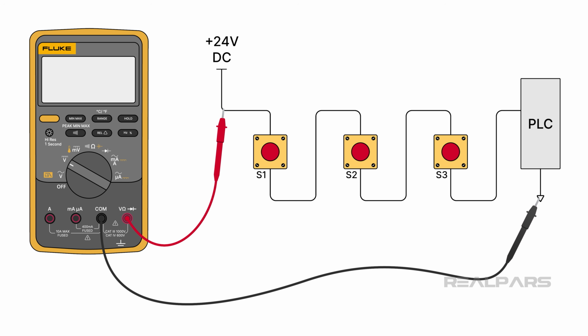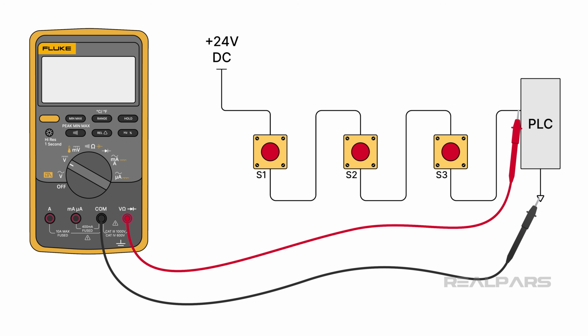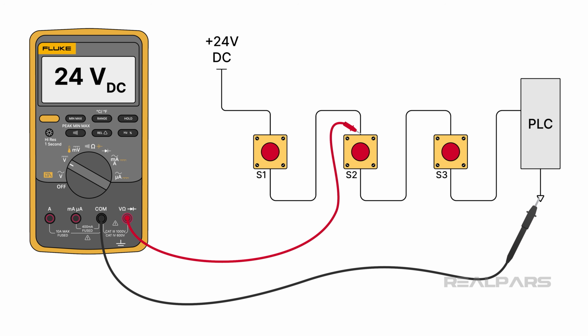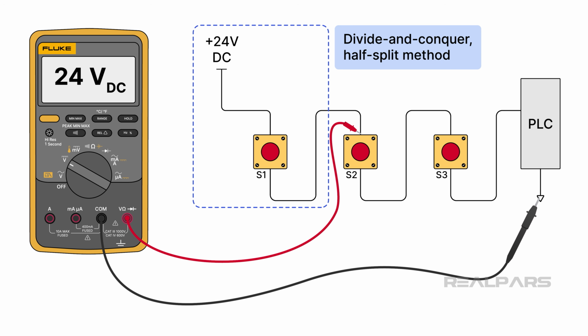You could start at the power supply or at the sensing end. Seasoned troubleshooters will tell you to start in the middle, thereby eliminating half of the circuit right away. This is called the divide and conquer half-split method. It cuts your troubleshooting time in half by confirming the correct operation of half of the circuit.